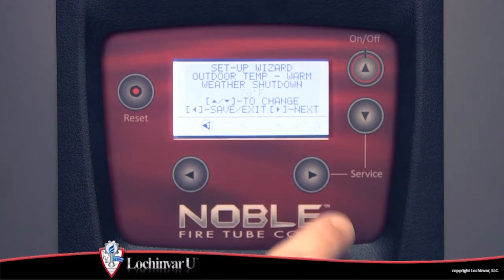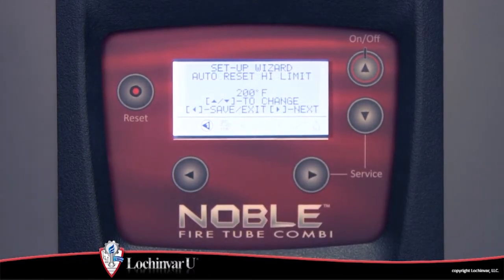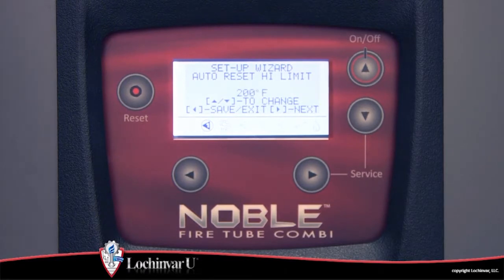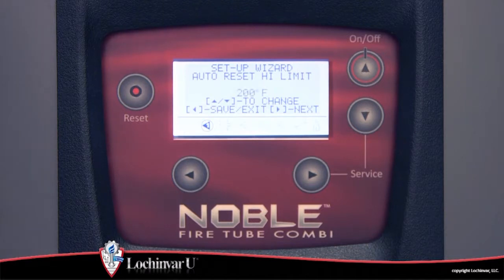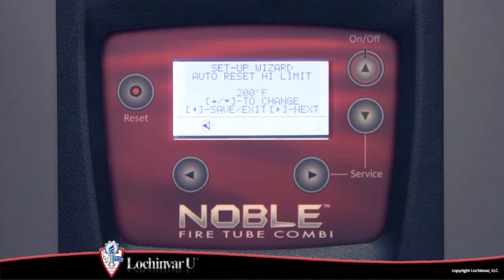The sixth parameter visible is auto reset high limit. When the outlet water temperature exceeds the setting of the auto reset high limit parameter, the unit will shut down and remain in lockout until the outlet water temperature falls 10 degrees Fahrenheit below this setting and a 60 second timer has expired.